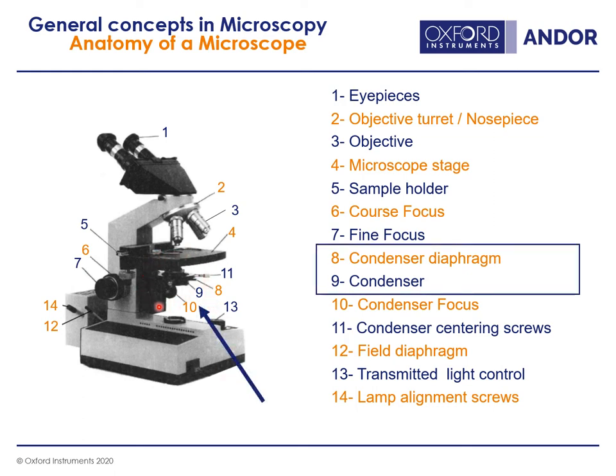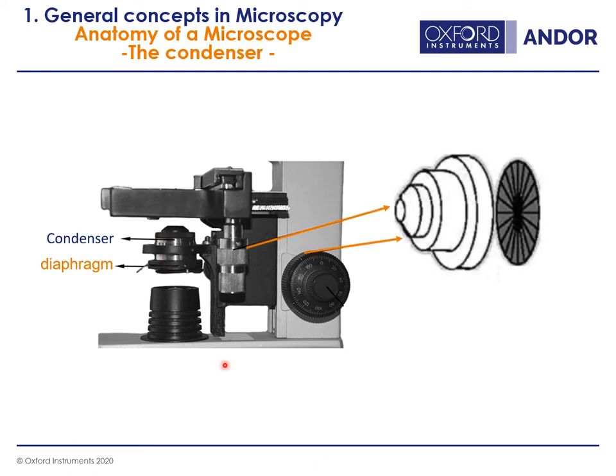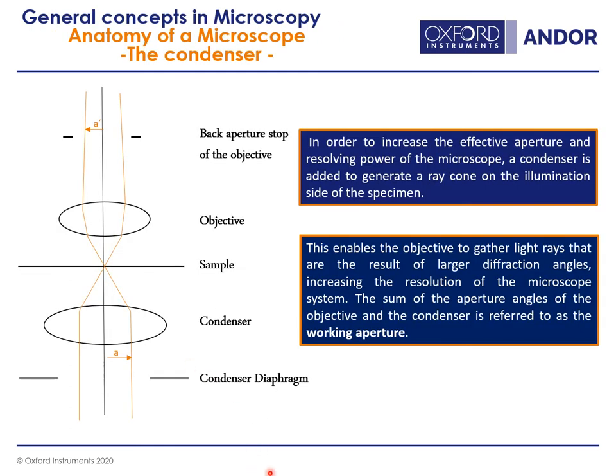The condenser sits on the bottom of the stage. The diaphragm is like an iris that opens and closes, allowing more or less light through the condenser to the sample. In order to increase the aperture of the objective and the resolving power of the microscope, the condenser increases the angle of the light rays captured that go to the sample, and therefore increases the angle of light captured by the objective, increasing the resolving power.